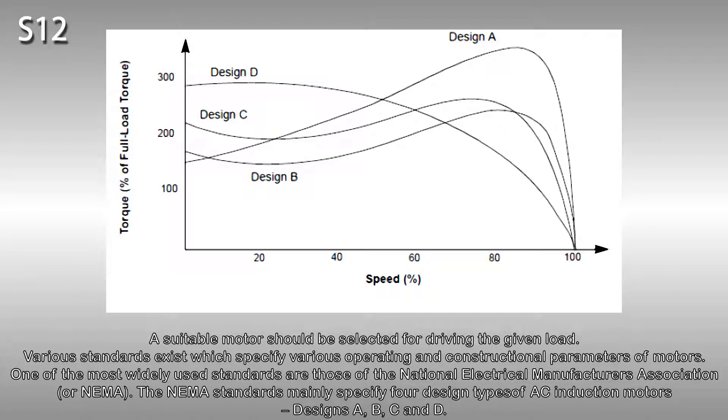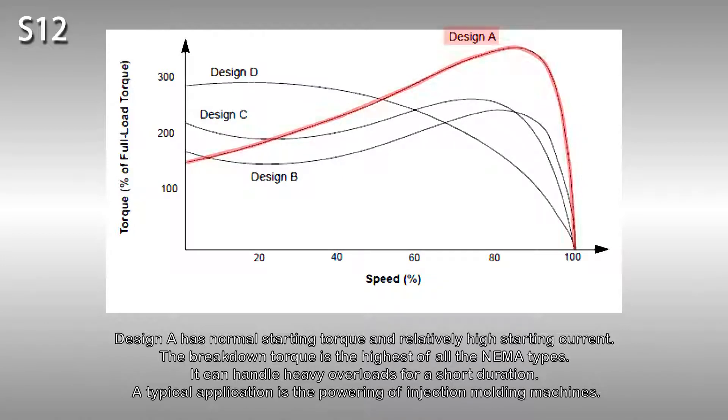The NEMA standards mainly specify four design types of AC induction motors: designs A, B, C and D. Design A has normal starting torque and relatively high starting current. The breakdown torque is the highest of all the NEMA types. It can handle heavy overloads for a short duration. A typical application is the powering of injection molding machines.